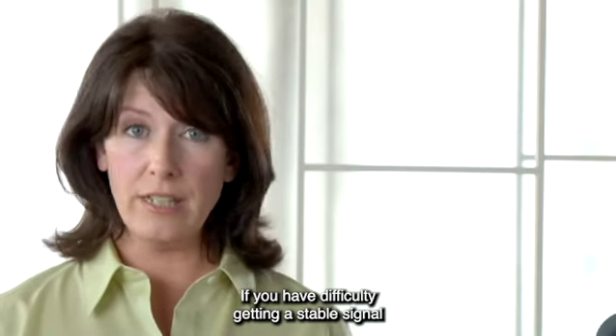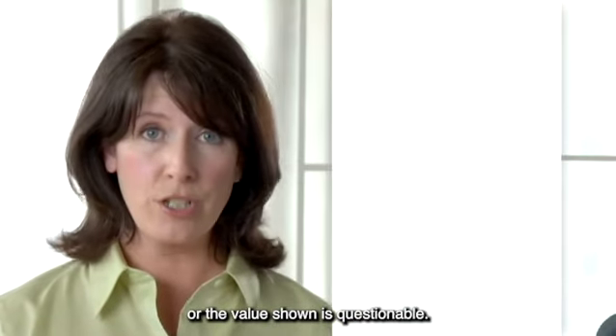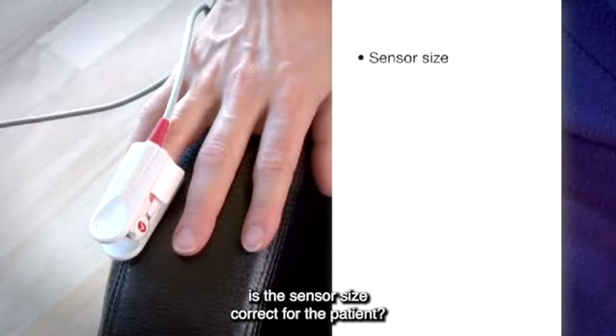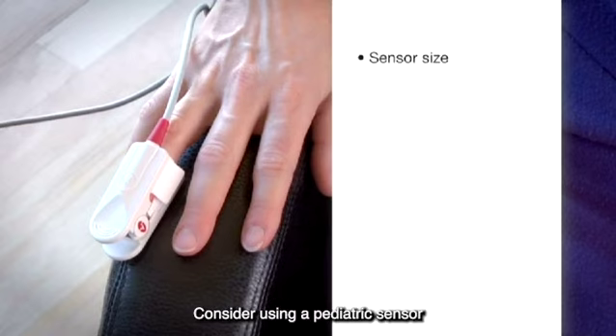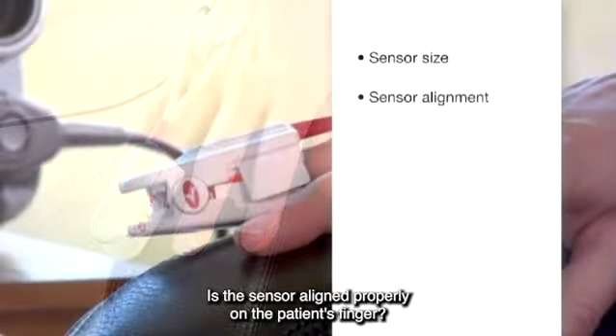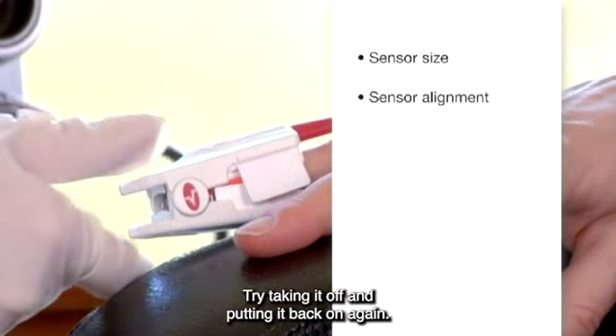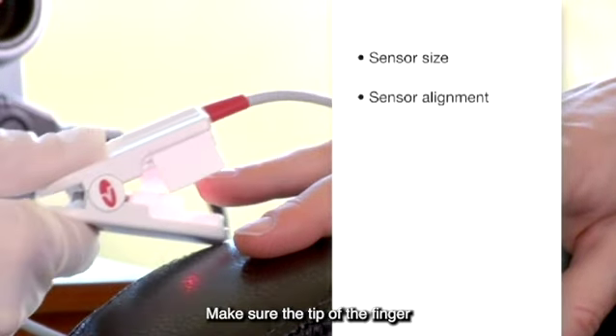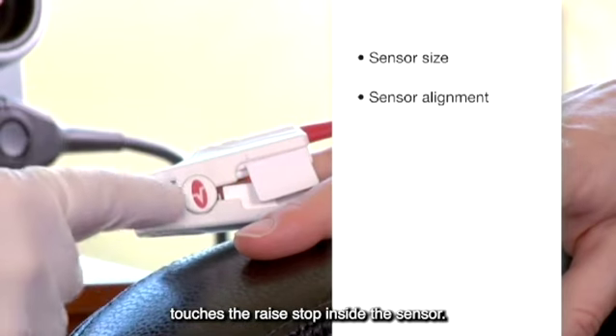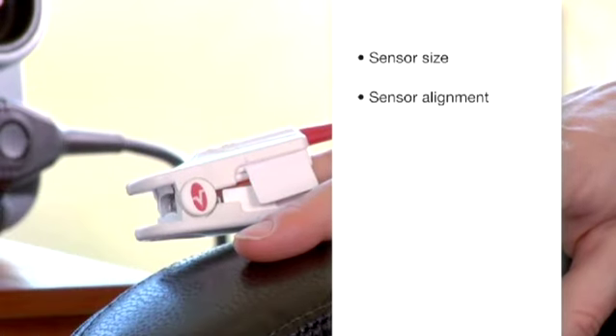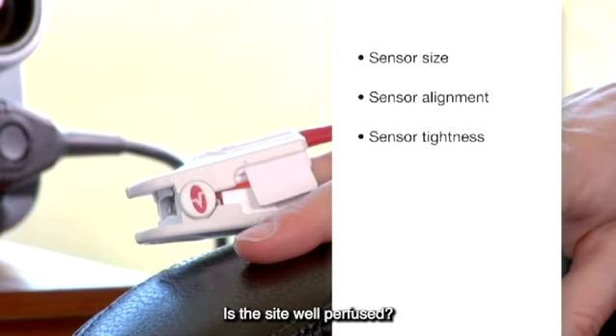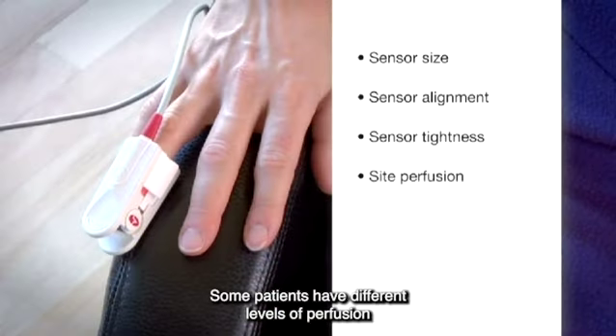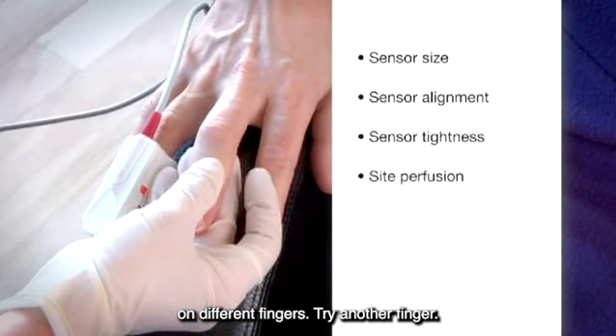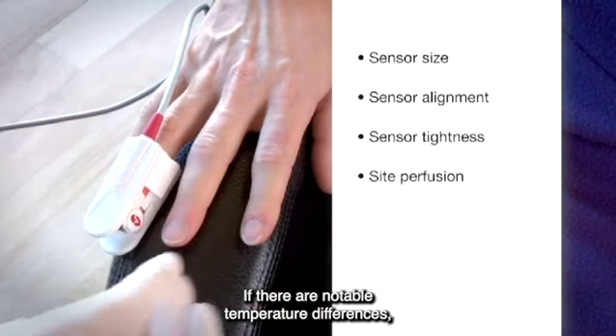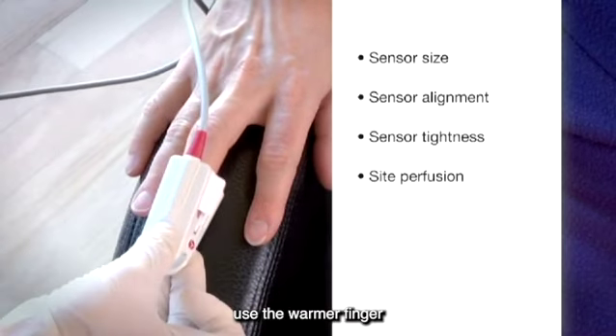If you have difficulty getting a stable signal or the value shown is questionable, consider these factors. Is the sensor size correct for the patient? Consider using a pediatric sensor for adults with small fingers. Is the sensor aligned properly on the patient's finger? Try taking it off and putting it back on again. Make sure the tip of the finger touches the raised stop inside the sensor. Is the sensor too tight? Is the site well perfused? Some patients have different levels of perfusion on different fingers. Try another finger. If there are notable temperature differences, use the warmer finger.